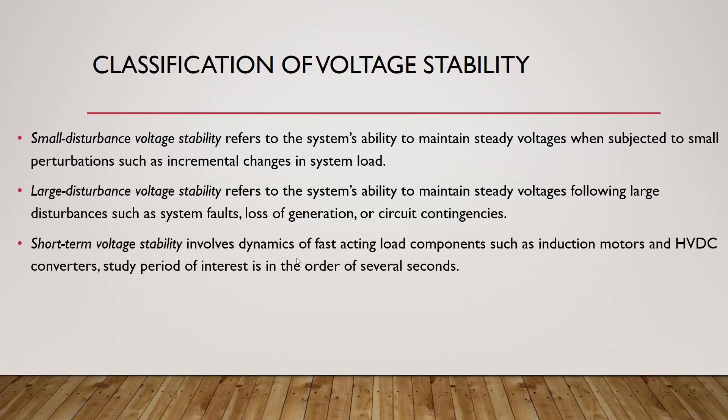Number three is short-term voltage stability, which represents the dynamics of fast-acting load components. Short-term means that instability occurs very fast. This involves components such as induction motors controlled by inverters — where the speed and torque of motors can be controlled by the inverter — components that act very fast within a very short time.